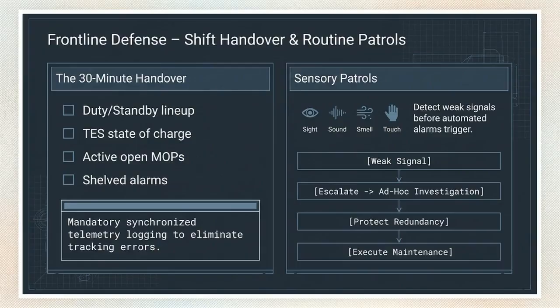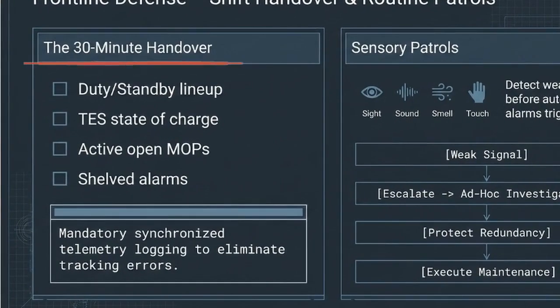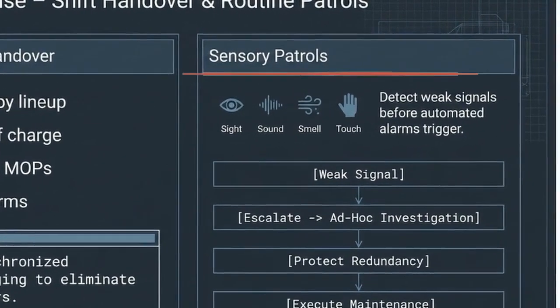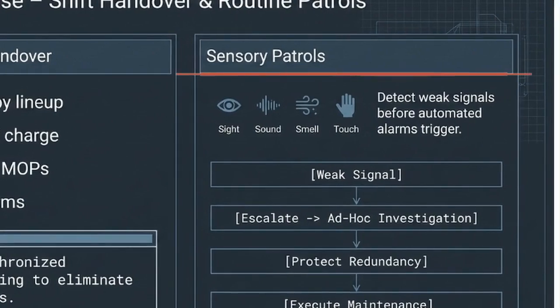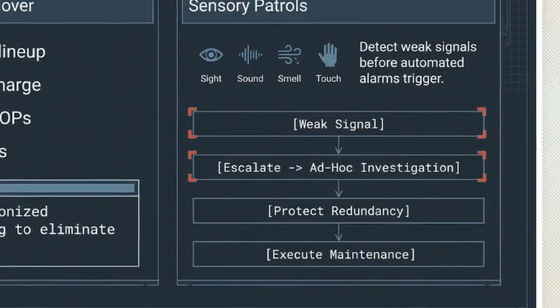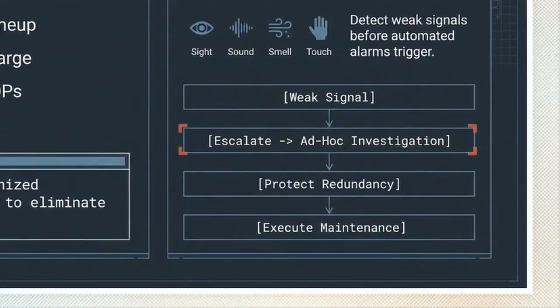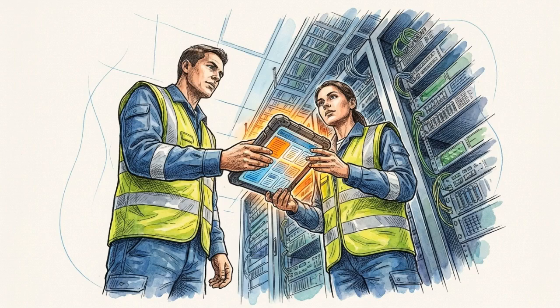The highest risk of failure occurs during human shift transitions. To eliminate tracking errors, incoming and outgoing teams execute a mandatory 30-minute synchronized handover, logging active alarms, bypass states, and ongoing maintenance. Beyond digital monitoring, frontline defense relies on sensory patrols. Operators use sight, sound, smell, and touch to detect weak physical signals, like the scent of burning insulation or an irregular pump vibration, long before automated alarms trigger an escalation. Early detection through direct human vigilance, combined with strict handover protocols, forms the first line of defense against compounding mechanical failures.